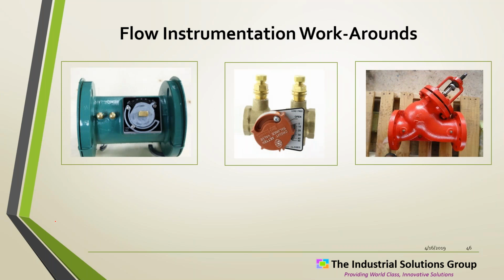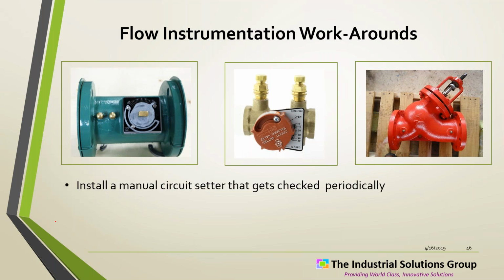I know one of the stumbling blocks is on flows. Flow meters can get expensive, but there are some workarounds. There are some devices you can put in the lines that are more manual, kind of like an orifice plate, that give you an opportunity to take some readings maybe once a month or so to cross check and make sure the flows are right. You could assume that the flow is going to be right in between readings, so that's a way to save some money.